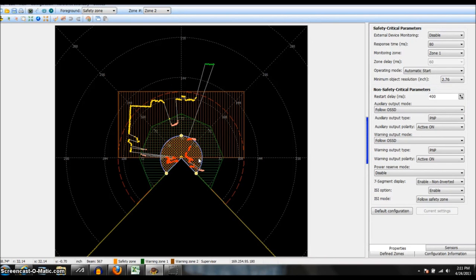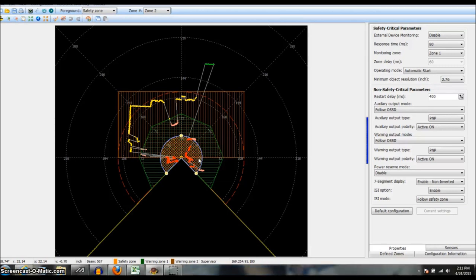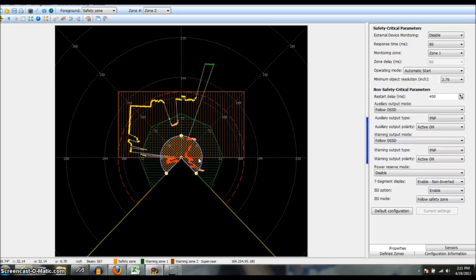To switch between different zones you use the digital inputs. You cannot switch between zones using the ethernet protocols. It has to be from discrete IO. The OS32C has 8 discrete inputs. We switch between zones by using any combination of these inputs being on or off.